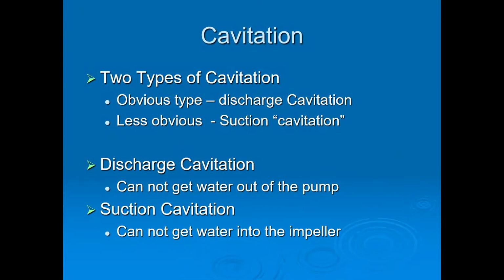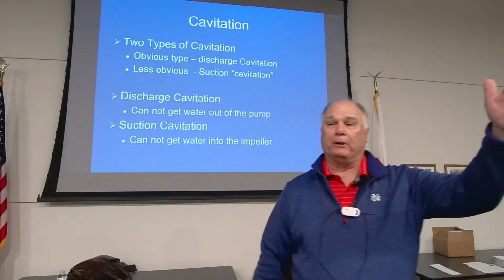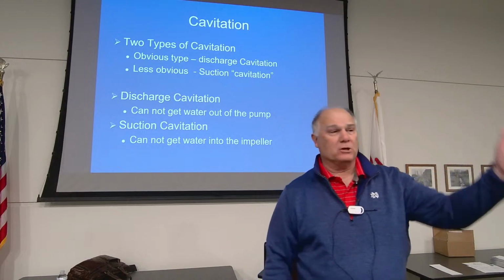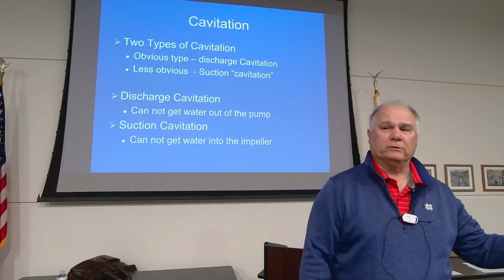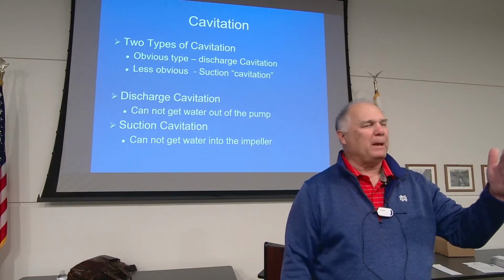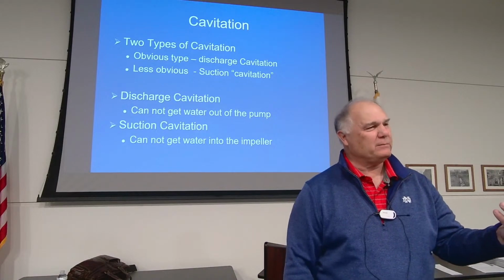Then we've got to talk about cavitation. Most people are aware of discharge cavitation. What's discharge cavitation? That is the inability of that pump to get the water out of the pump. That's all the stuff to the left side of the curve, that big yellow dashed line we talked about. You never want to operate over there. There's also something called suction cavitation that people sometimes see, but sometimes they really don't.